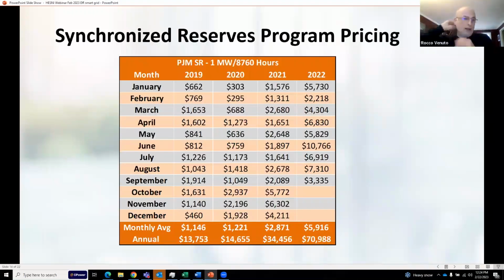There's another program beyond the emergency program called synchronized reserves. This typically isn't a great fit for hospitals, but I've seen a couple instances where it did work, so I'll mention it. Synchronized reserves is run not based on whether there's going to be an outage or how much it costs, but on whether a disruption on the grid can be resolved with a short-term, usually less than 10-minute reduction in power from strategically located sites that can respond quickly. If sites can respond within essentially 8 minutes, we automatically dispatch them to reduce power. That lets us moderate grid disruptions and bring hertz and voltage levels back in line when there's been a destabilizing effect on the grid. That's the Sync Reserves program, a quick response program.